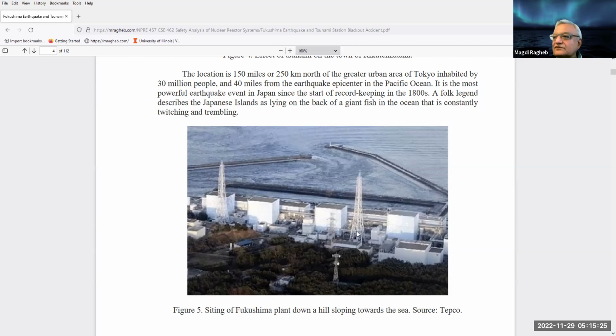Those towers were basically interconnected for the ventilation of the plant itself. One design flaw we'll see as we go along is that the ventilation ducts were directed from one unit to another, and those ducts carried hydrogen. So in one plant where there was no real damage occurring, hydrogen directed in from another unit became what's called a common cause failure.